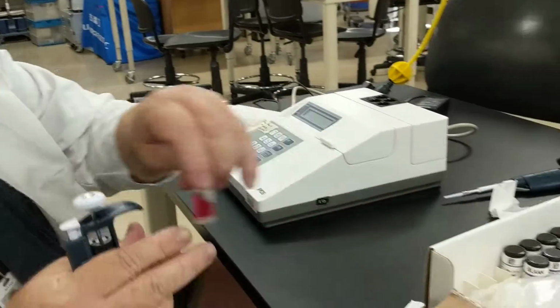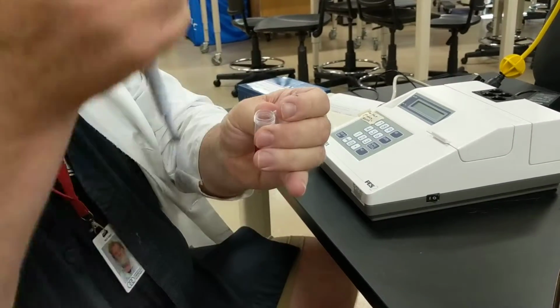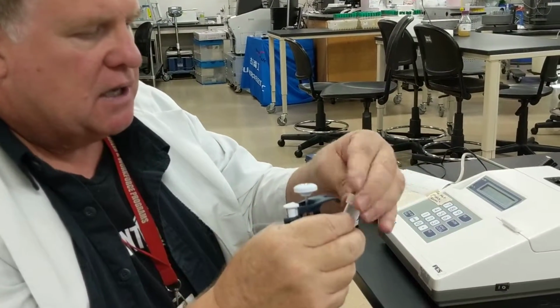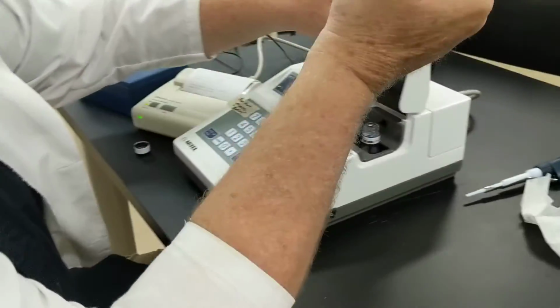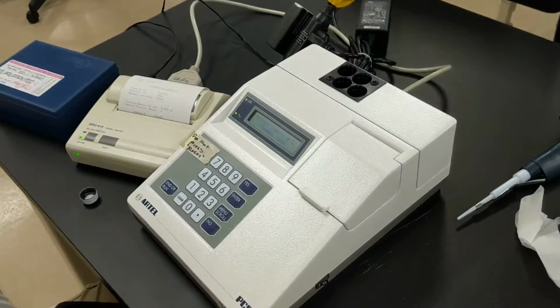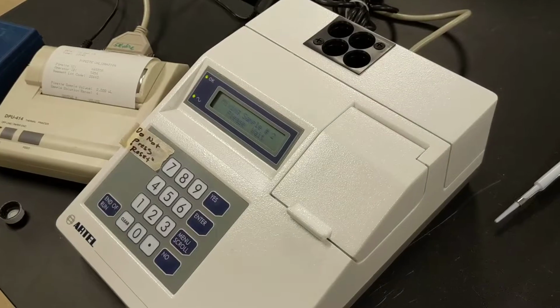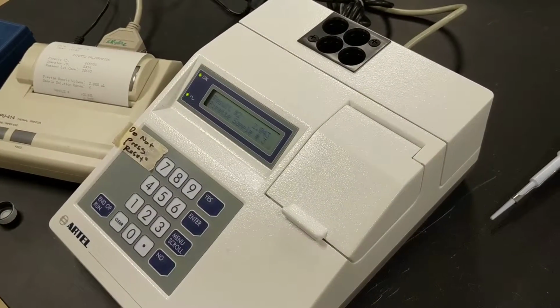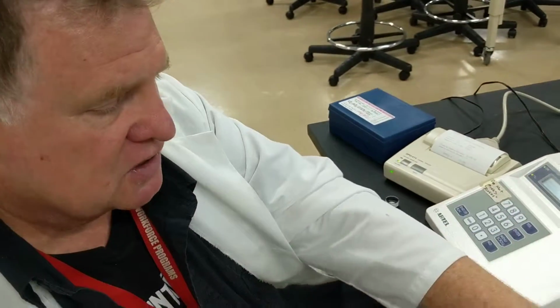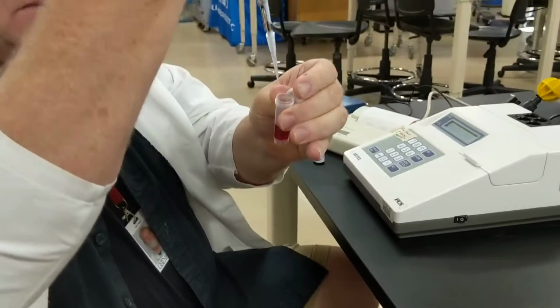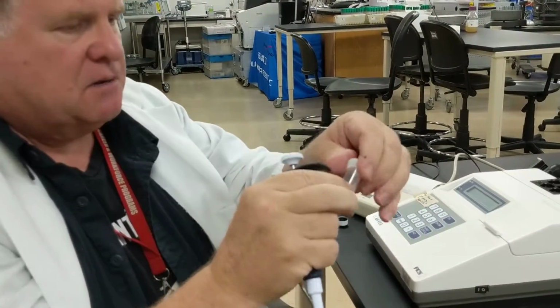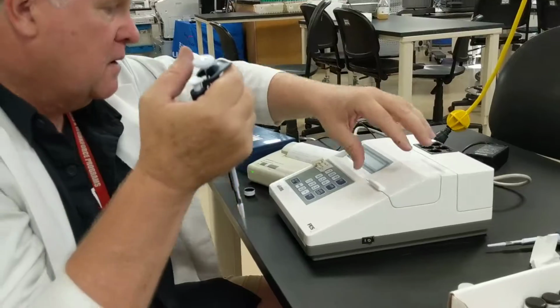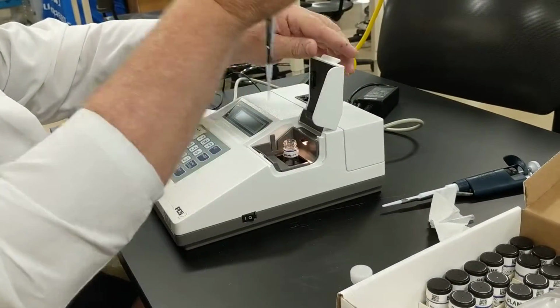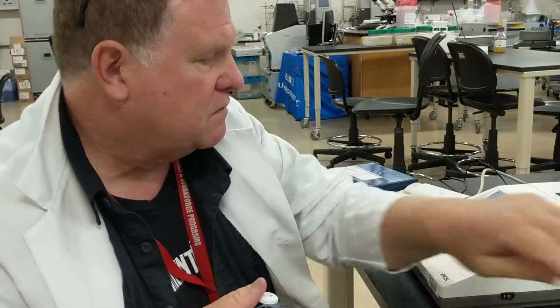I'm going to take this sample out. I'm going to go ahead and pipette out. That looks more like 2 microliters. I am then going to put it in my tube, make sure it's all gone, put it down, and it's reading sample 2, 2.043, so that's within calibration. And so I'm going to do it one more time. My tip. And so normally what I would have us do is that on each one we would do it 3 times.